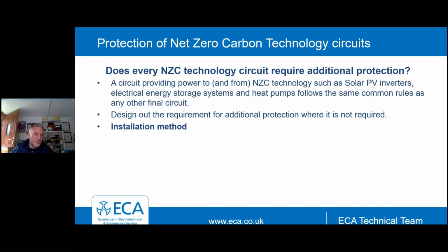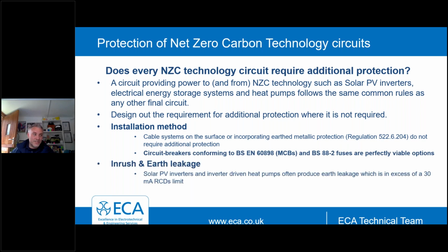Do we need additional protection on every circuit? And from experience, the answer to that really is probably very few circuits require additional protection, unless you've put cables in walls or you've installed it in a manner that requires additional protection by RCD. The simple thing with this is to design out that RCD element where it's not required. You may need them for fault protection, in which case you should find a suitable RCD to provide that. But in many cases, a circuit breaker conforming to 60898 or BS 88 fuses are perfectly viable to give you the protection you need, the ADS you need for that device. Also, designing out RCDs, especially with heat pumps as an example, eliminates the need to consider inrush and earth leakage, which can be a big problem.